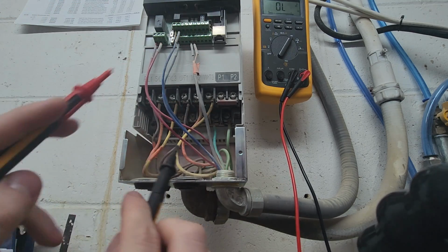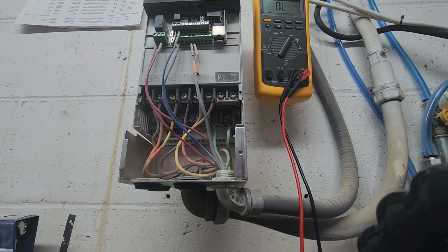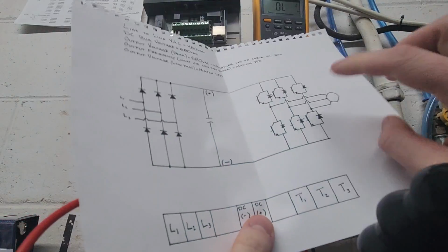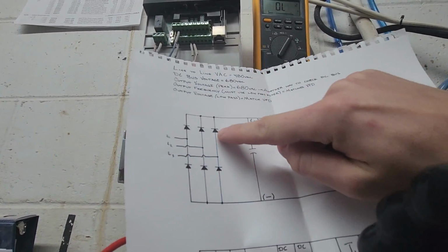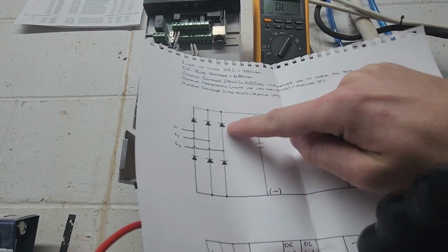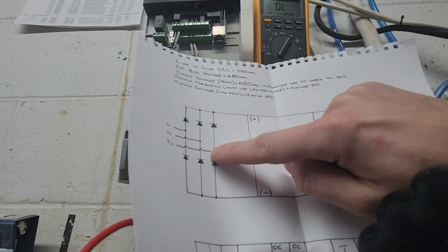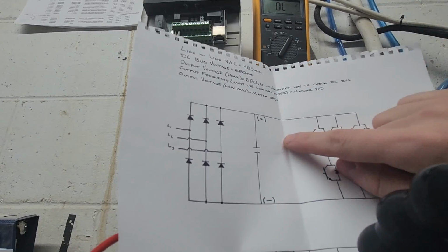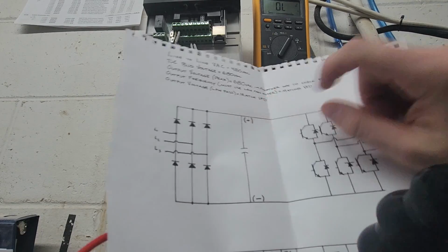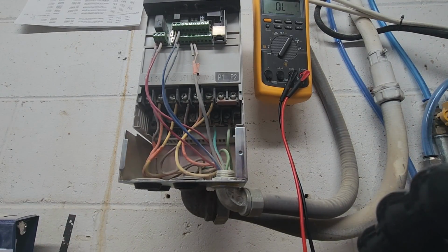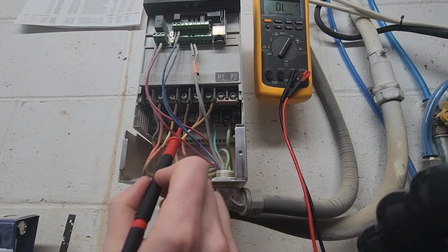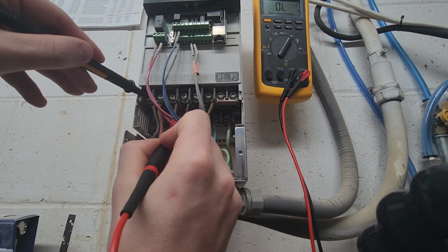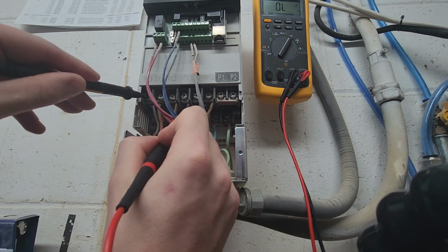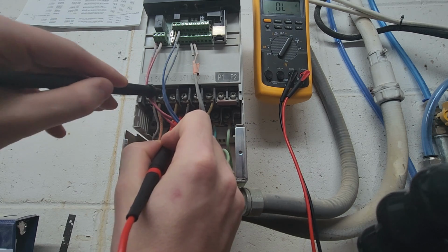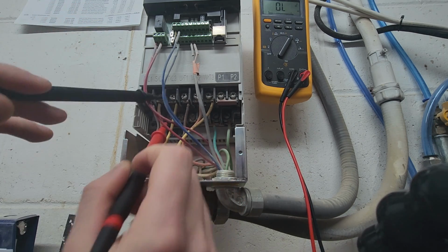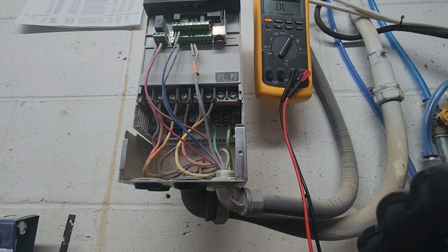Now we're gonna flip these electrodes around. So we'll be trying to send pixies back this way. And if these diodes are working properly, they're basically electron check valves, so you shouldn't be able to get electrons through your diodes back that way. So we're going to put our positive lead here and our negative lead here, and we should get over limit on our multimeter. So positive on your DC bus positive, and L1 with your black electrode, L2, L3, and we're over limit on all three of those, which is perfect.